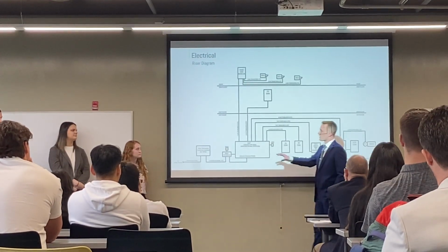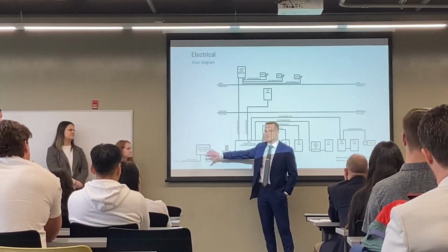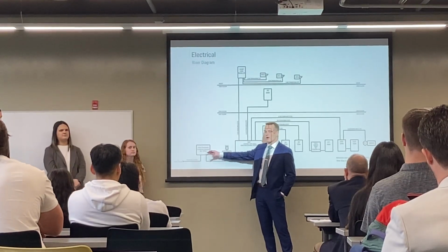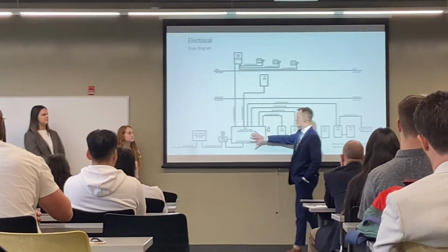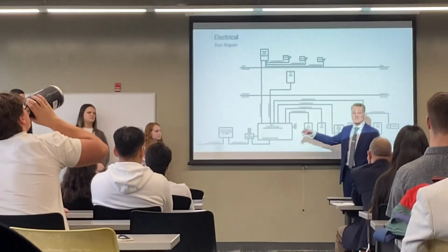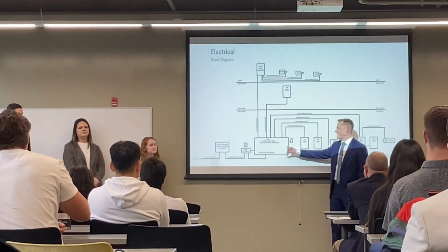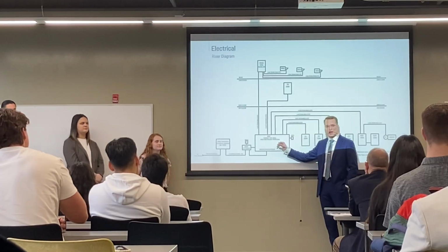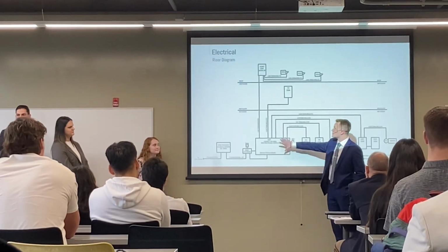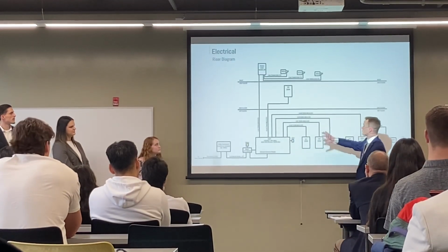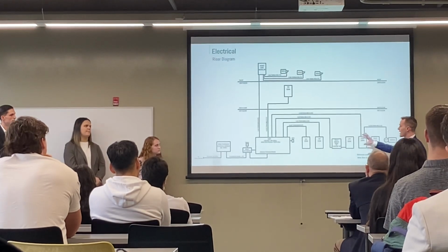So first, over here, we have our utility transformer, so it's 12,470 volt coming into 120/208 volt, and that runs to our main distribution panel, which is a 120/208 volt three-phase 4-wire panel. It has an SCCR rating of 25 kiloamps. And then from the main distribution panel, we distribute power to 6 panels that kind of power the whole building.